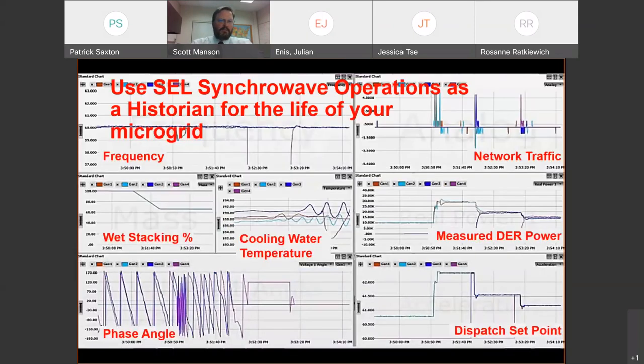Okay, another example. In this exploration of how we come to a grid that is inverter-based, renewable, how do we get to that point? This is not an easy question to answer. We discovered we had the tools we needed, SEL. There's a piece of software we called SynchroWave Operations. Beautiful historian for the life of your inverter-based resource or microgrid. Very low-cost piece of software. We put it on an SEL or a third-party computer, and it collects what's called high-speed time-sampled, time-aligned events called synchrophasor data. This data was intended to help us understand the oscillations and the strange phenomena we see in a power system. Aha, sounds like an inverter, sounds like a renewable.